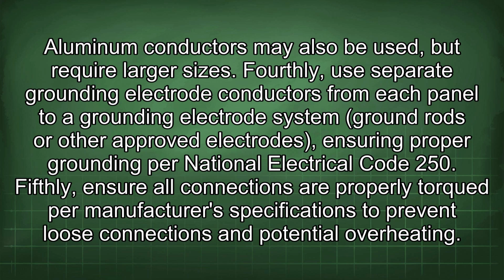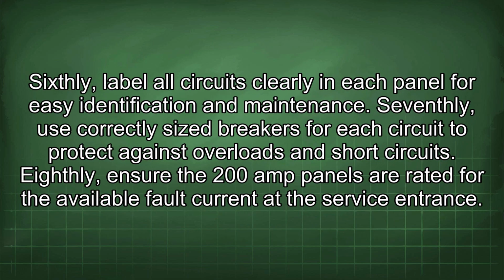Fifthly, ensure all connections are properly torqued per manufacturer's specifications to prevent loose connections and potential overheating. Sixthly, label all circuits clearly in each panel for easy identification and maintenance. Seventhly, use correctly sized breakers for each circuit to protect against overloads and short circuits. Eighthly, ensure the 200 amp panels are rated for the available fault current at the service entrance.